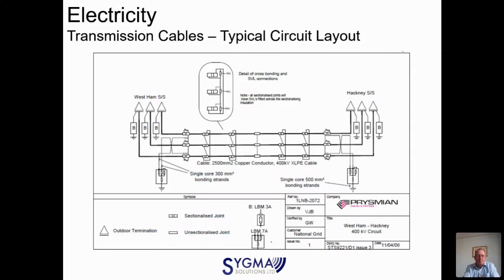SBLs is one. An SVL is a sheath voltage limiter. Because of such high voltages, you get massive amounts of induced power onto the armor of a cable. I put a post up on LinkedIn and our Facebook utility page a while ago of fiber optic cable that was arcing. That arcing was caused by induced 60 hertz. It was in the States. So imagine when you've got the outside of a cable, which is next to 400 kV single core, you're getting a huge amount of induced voltage.